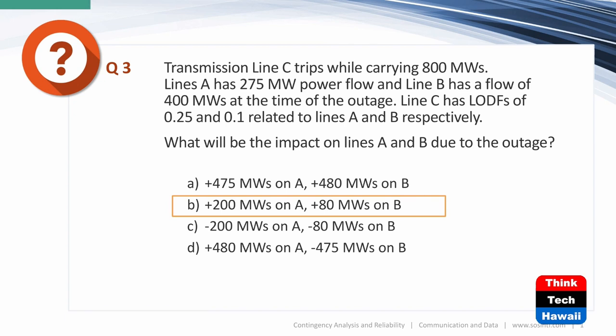The impact on line B: it's a 0.1 Line Outage Distribution Factor, so one-tenth of 800 megawatts is 80 megawatts. Notice that answer C is a detractor — it's the one that tricks you if you think the flow is being lost, but it's not. When you lose one of three parallel lines, that flow still has to find its way on the remaining lines since you haven't lost any load or source.